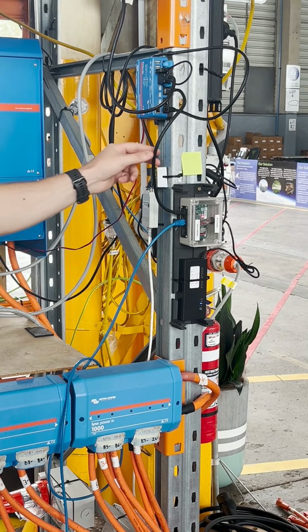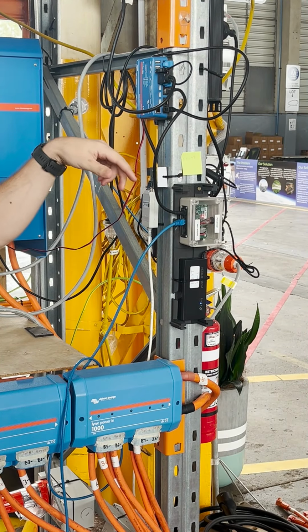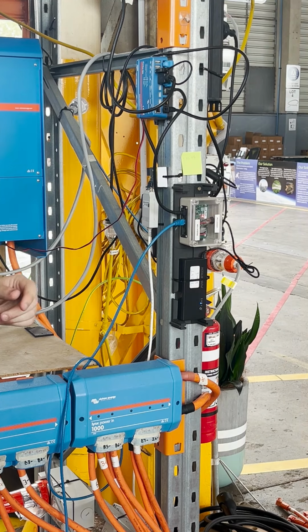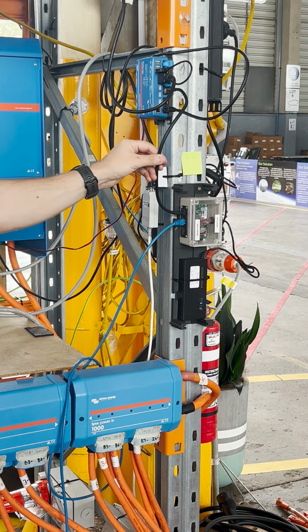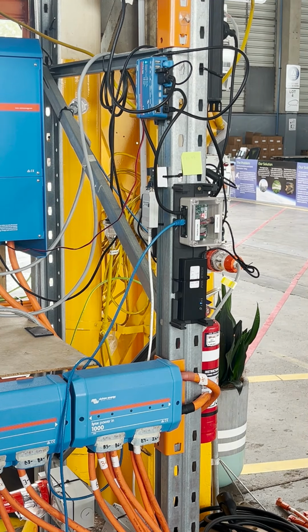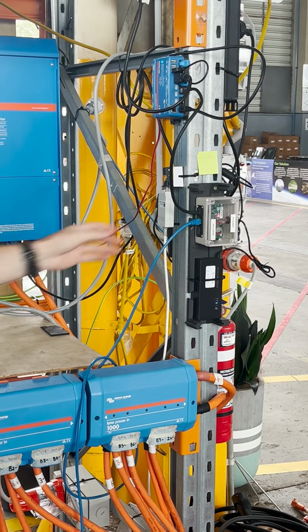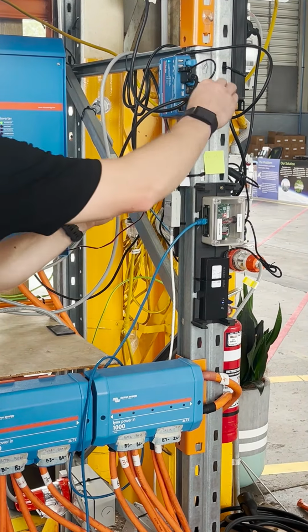The first thing to check is to make sure that you're using a genuine Type A or Type B VE.CAN cable from Victron. Here we're using a cable that I made, which has the correct pins, but you can see it's not connected, so obviously there's a mistake. So if I remove that cable...